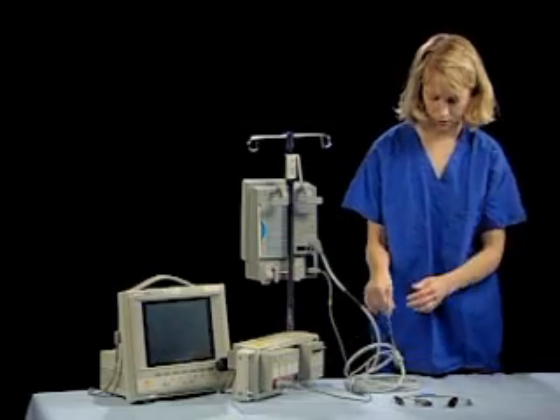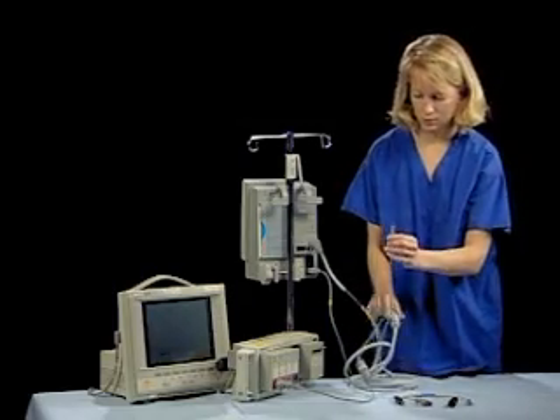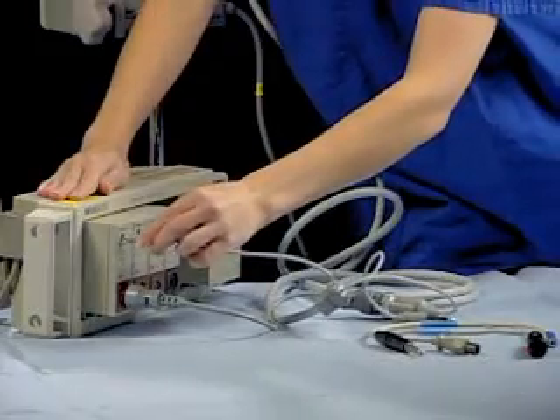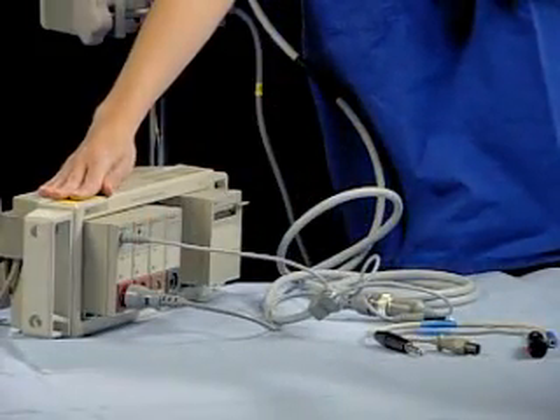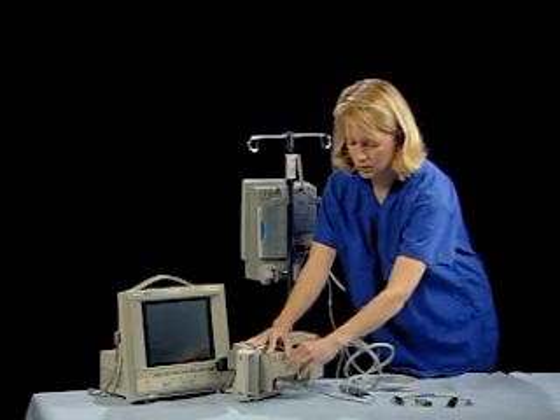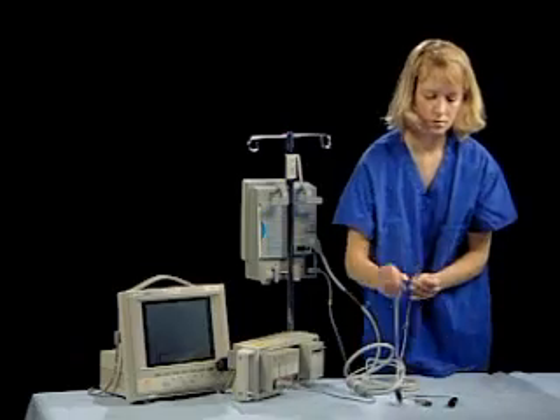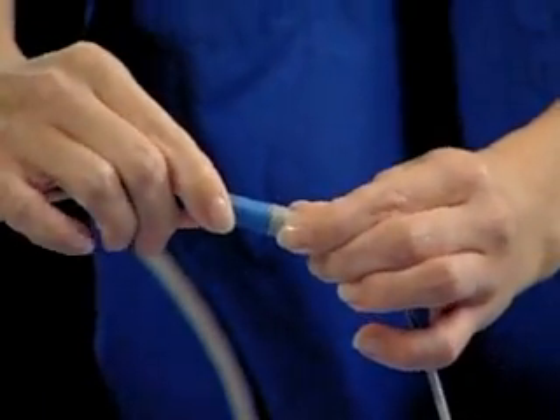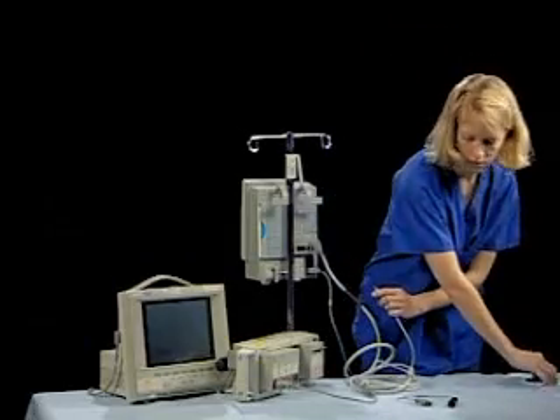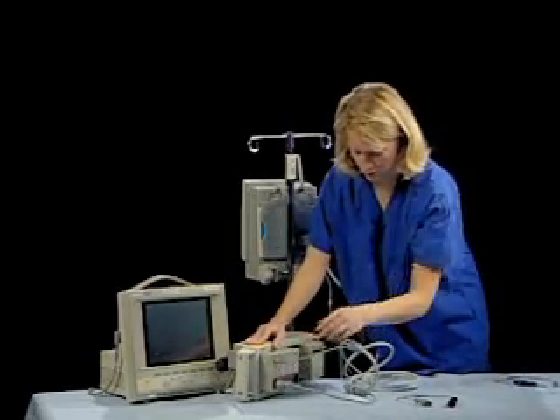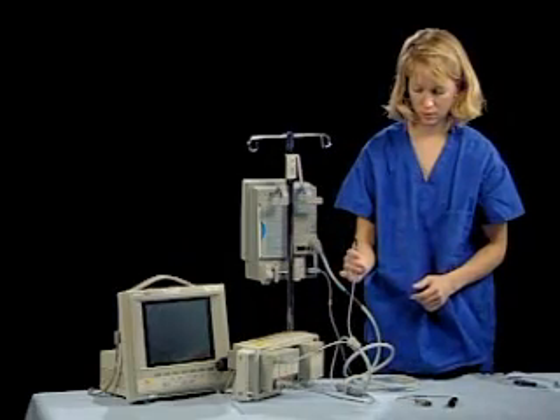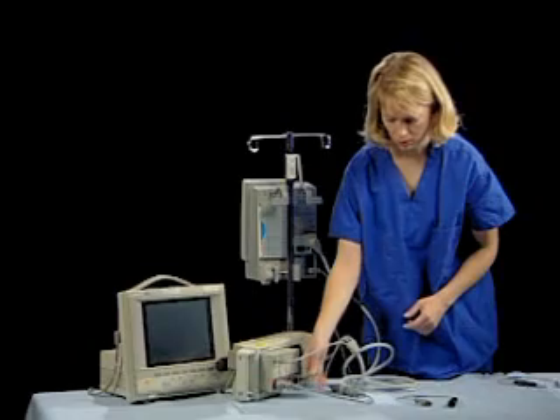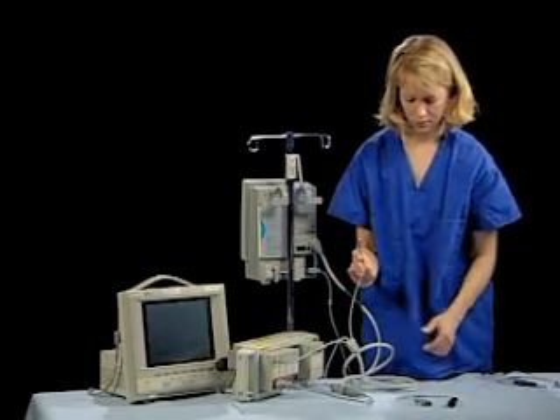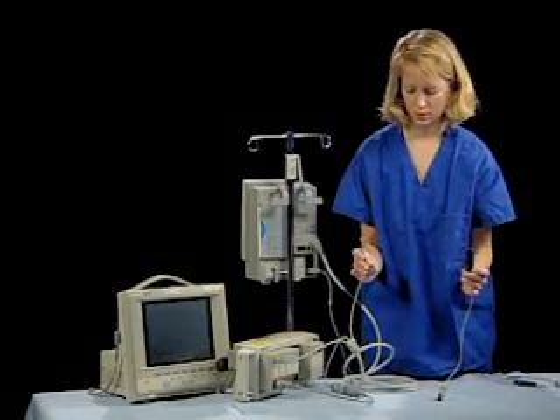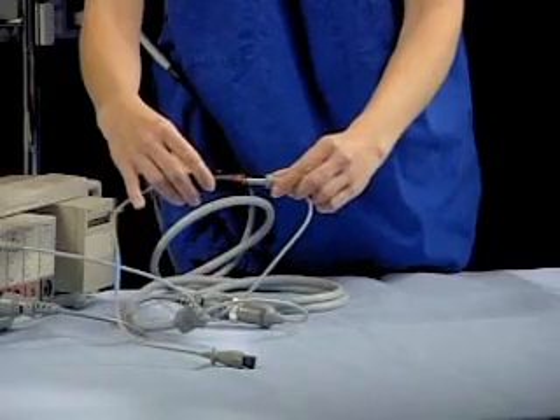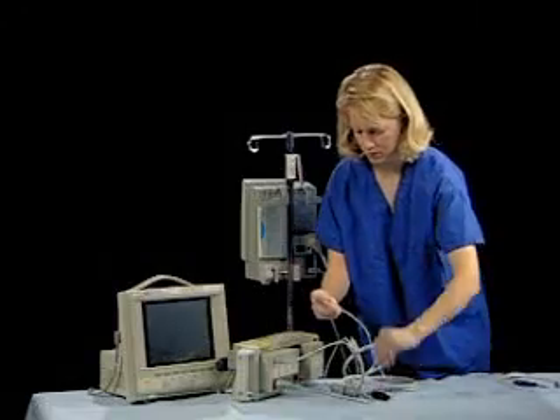The smaller of the jacks is the arterial pressure input line, which allows arterial pressure data from the bedside monitor to be used by the MPM-1 to calculate and display CPP. This connects into the arterial output of the bedside monitor and will require an adapter cable for your bedside monitor if it does not fit. The larger of the two jacks is the intracranial temperature output cable and is used only if the intracranial temperature is being monitored. This jack provides intracranial temperature data to the bedside monitor. It is connected to the temperature input on the bedside monitor and will require an adapter cable for your bedside monitor if it does not fit.